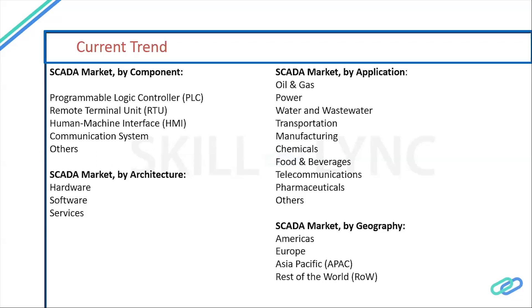Human Machine Interface (HMI): For HMI you don't need a full SCADA — it's basically a touchscreen with limited options. If your plant is very small, you can connect an HMI system and define it as per your requirements. HMI has no hard disk, only ROM, so there's very limited space — just enough to develop graphics or animations for live device status. If you need alarm events, report generation, or OPC integration, SCADA is required.